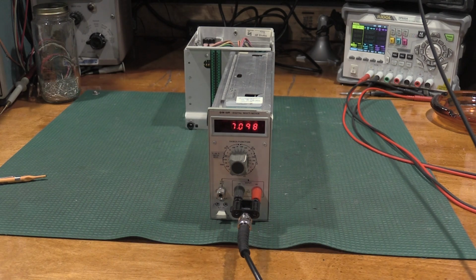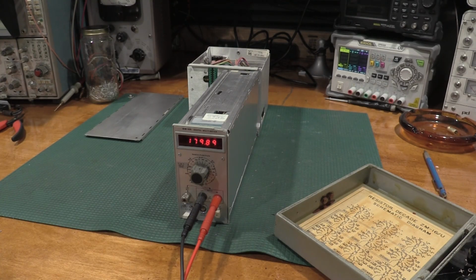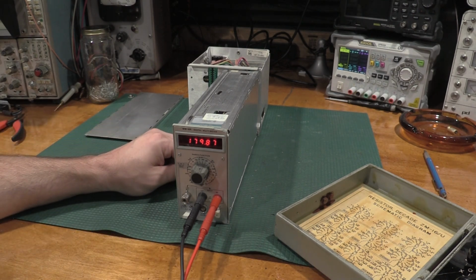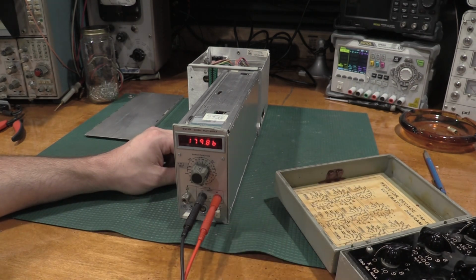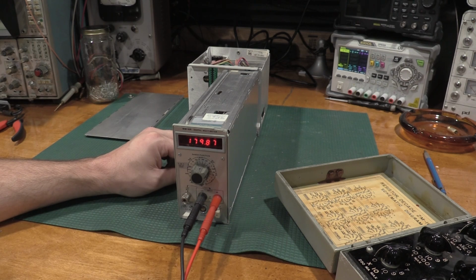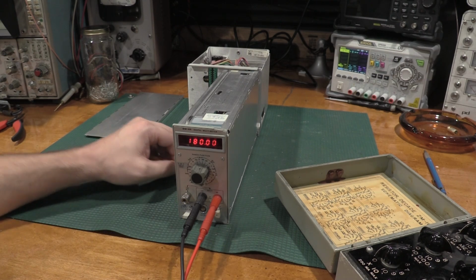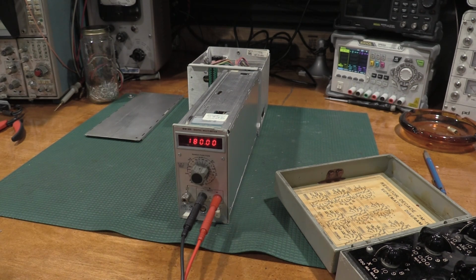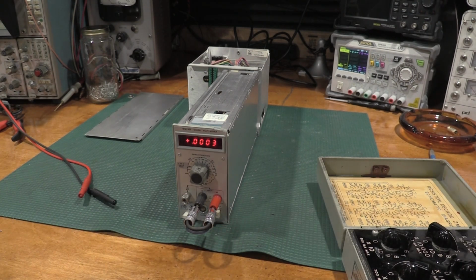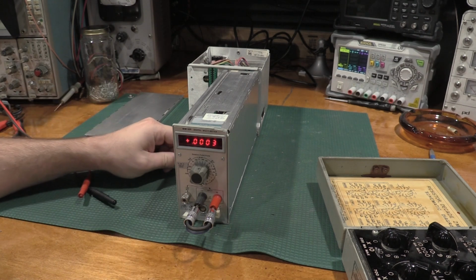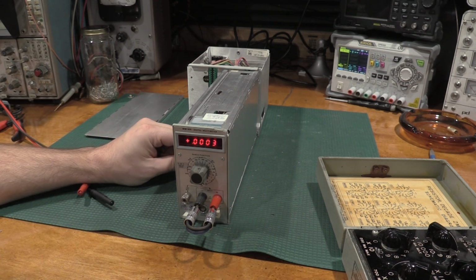So we'll take it from the top. Okay, so our record isn't broken yet. TM modules need repair or alignment. We'll do ohms real quick. My resistance box, which is right here, which is struggling, but I checked it on the 7500, is set to 1800. That's about as good as we're going to get it. That is a very fiddly control. And our current measurement 0 is off, so I need to adjust R50 to bring it down.